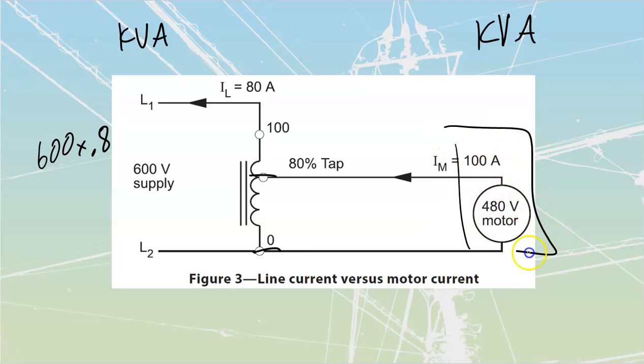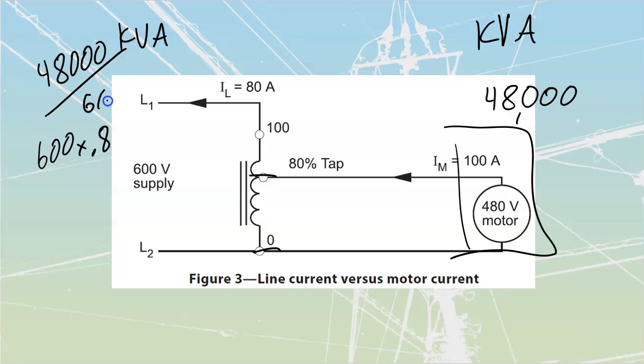That's going to be based upon the loads at 480 volts. If this gave me 100 amps at 480 volts, I could translate that into kVA. 100 times 480 gets me to 48 kVA, and I would have to have the same amount of kVA coming in. So I can just take that same 48,000 and divide it by 600.